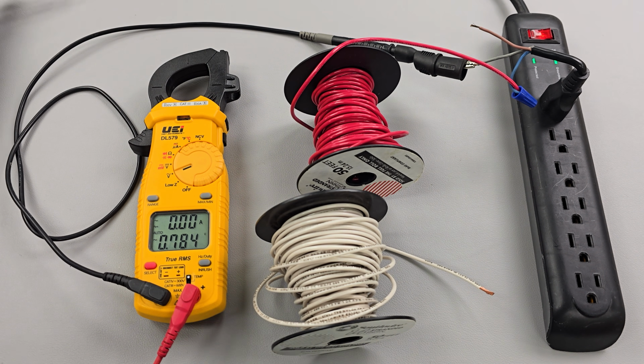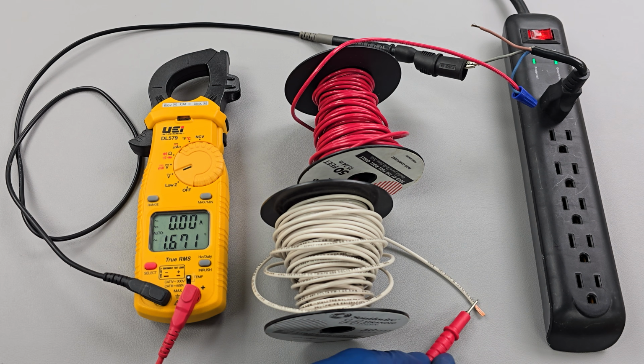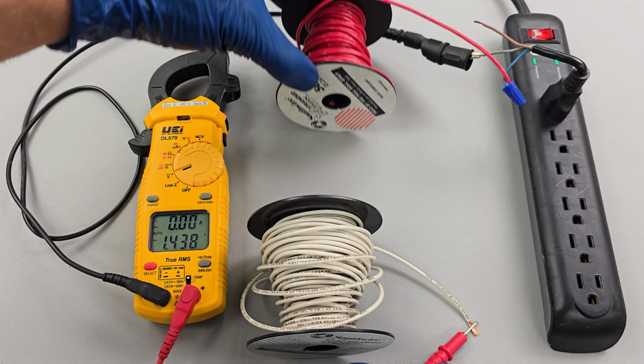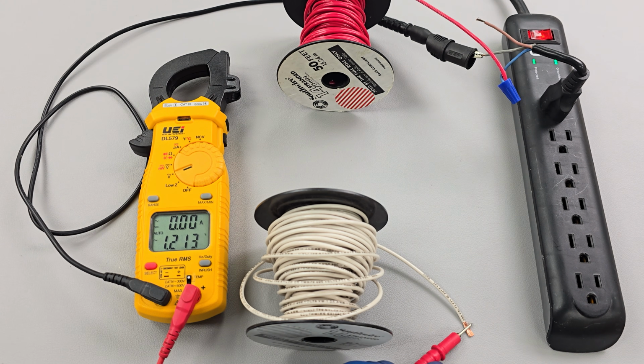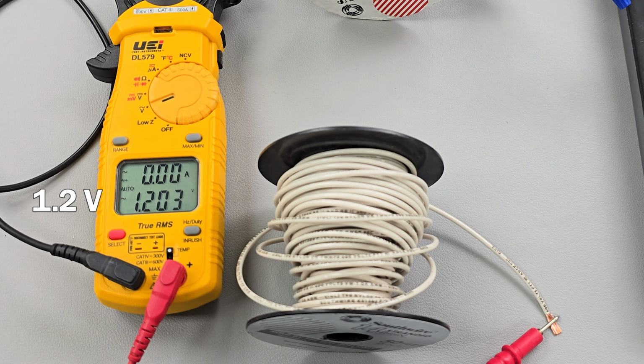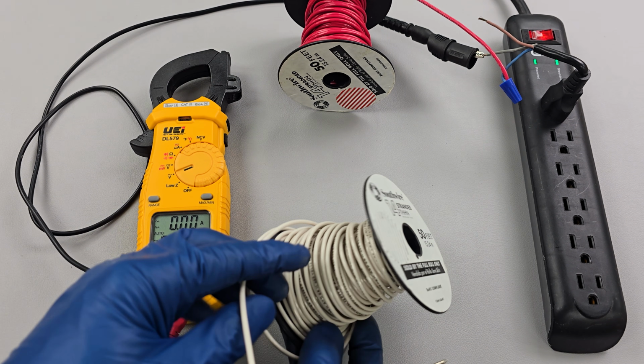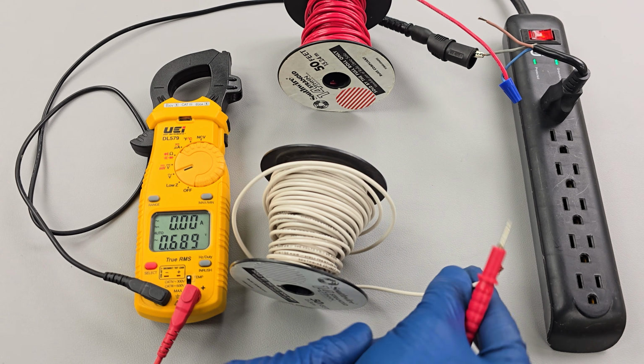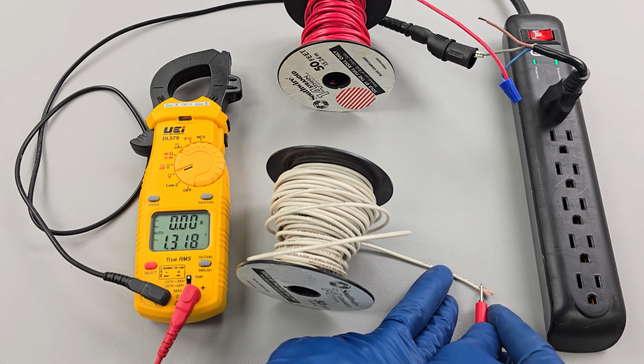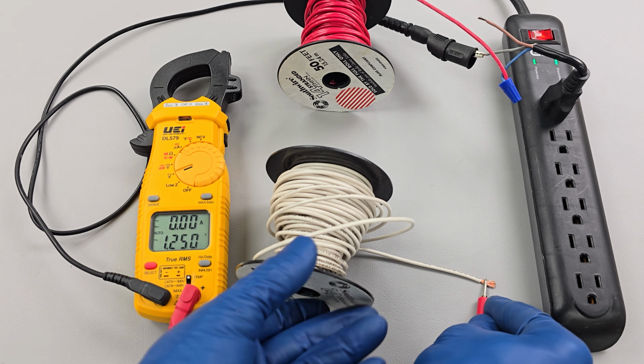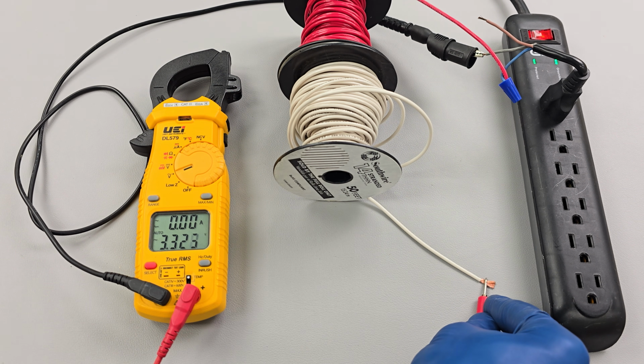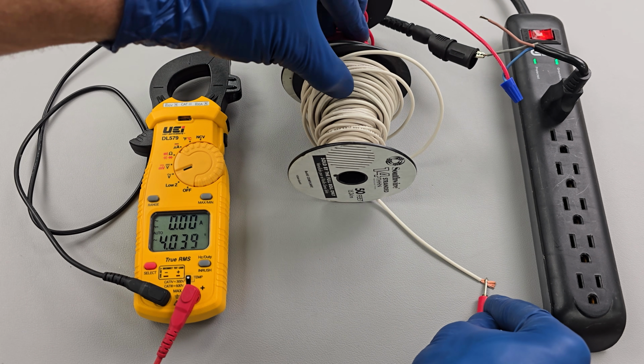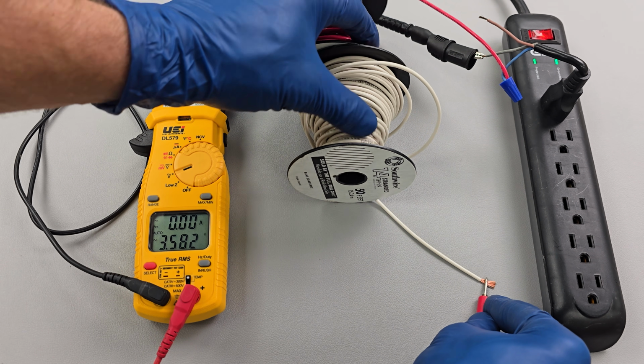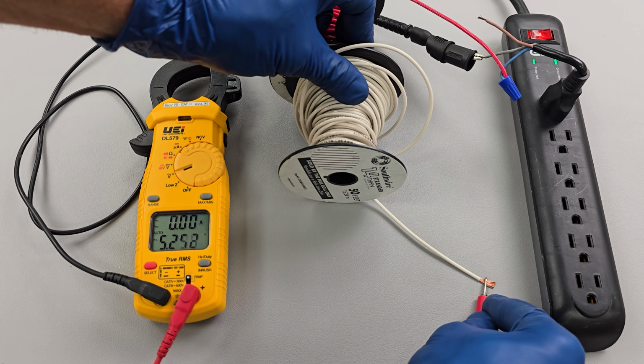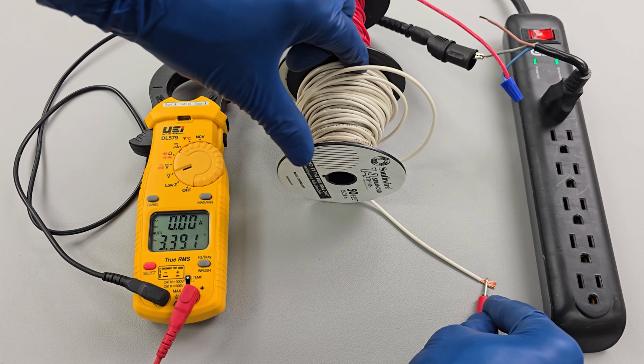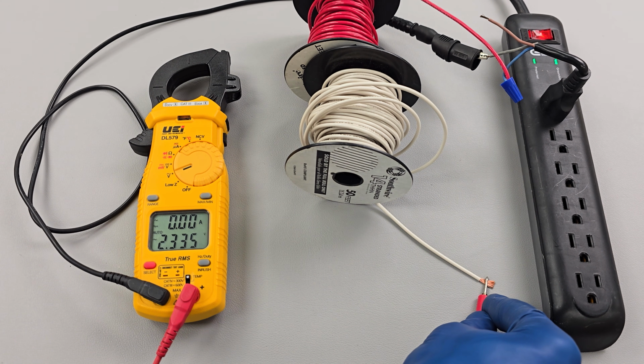So we have our voltage there, and we shouldn't have any voltage on this wire right here. But you see we do have voltage, right? So we've got 1.2 volts. So this is a phantom voltage. That's what that is. And so the closer we get this coil of wire to the red wire, it's going to be inducing electrical current into this roll. You see? As we're putting it closer and closer, and as we get the majority of the wires closer to each other, it's inducing a voltage. It's a ghost voltage into the wires. It's not enough to carry current. And so you can see it's not much voltage at all.